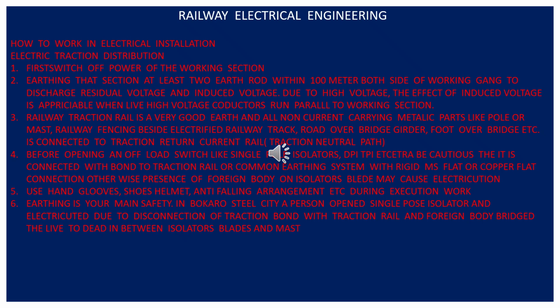It will not touch him. But the bond was open, maybe during engineering or some other means, and when he opened the isolator, the foreign body touched the blade to the mast and immediately he got electrocuted. So be serious. Before opening an isolator, first you see the bonding connection with the traction rail, or in a substation, it has two duplicate connections with the earth, with the common earthing system. It should not be cut, it should not be disconnected. Be very cautious about this. Okay.